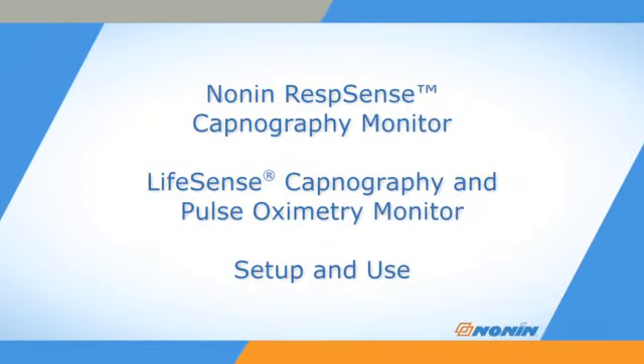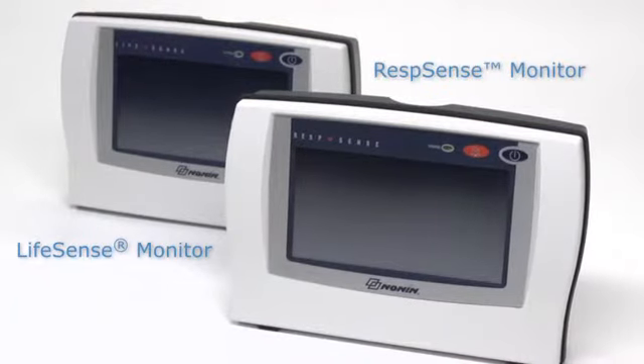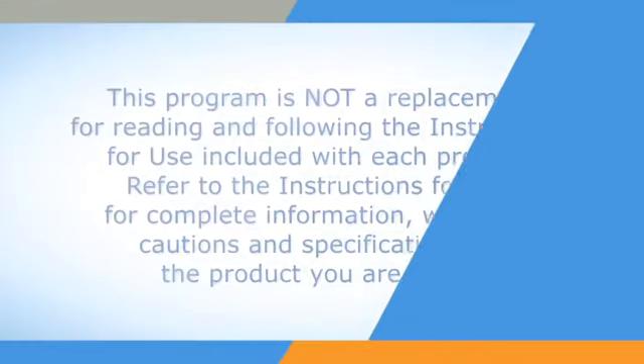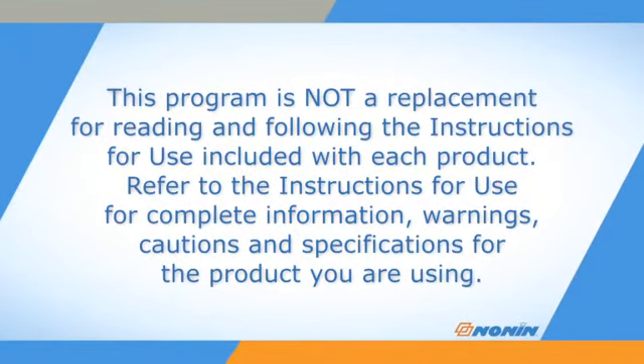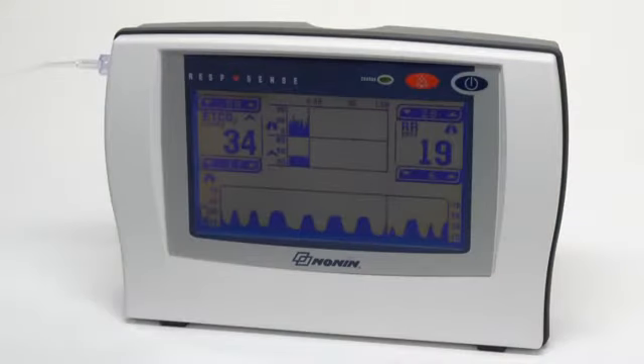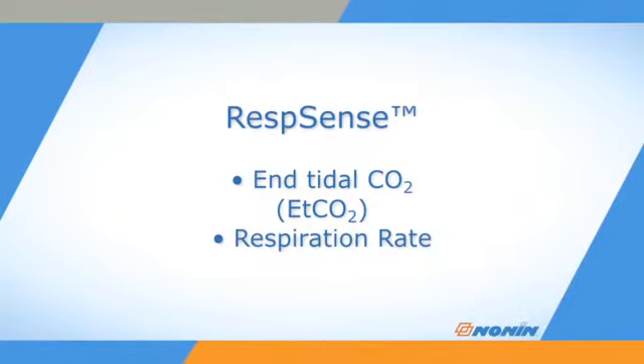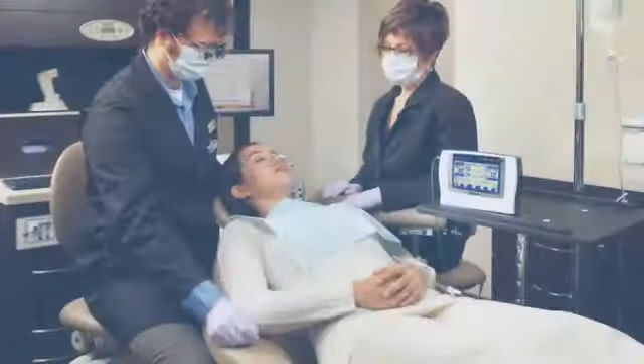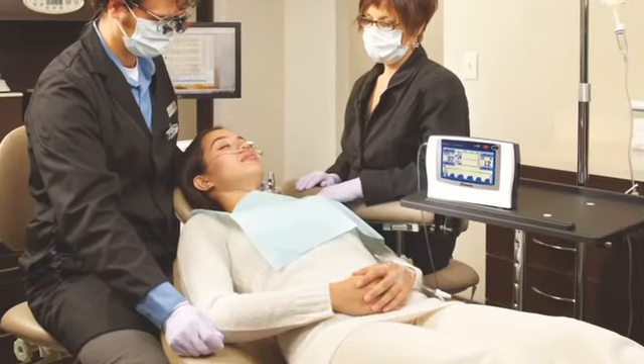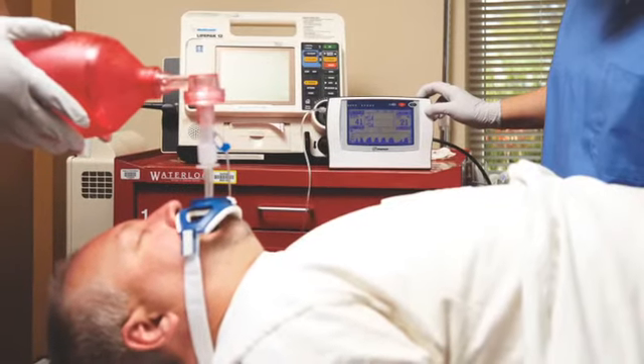This short video shows how to properly set up, connect, and operate the NONIN RespSense capnography monitor and the LifeSense capnography and pulse oximetry monitor. The RespSense monitor uses side-stream, non-dispersive infrared spectroscopy to continuously measure end-tidal CO2 and respiration rate. NONIN Medical's RespSense capnograph with proven CO2 detection technology offers the earliest indicator of an adverse breathing event.